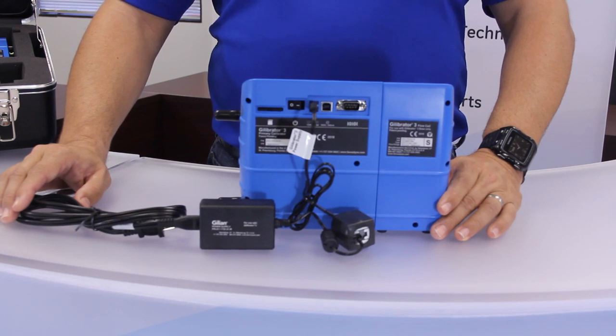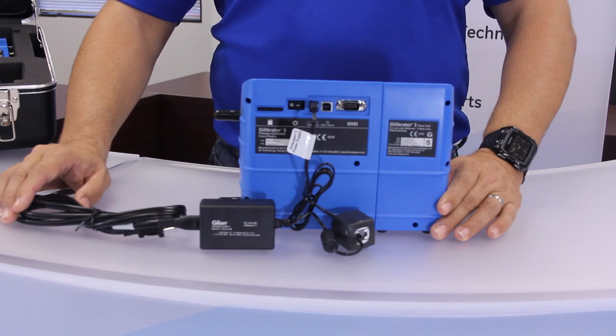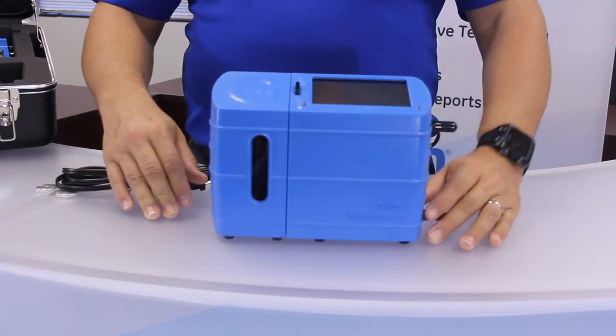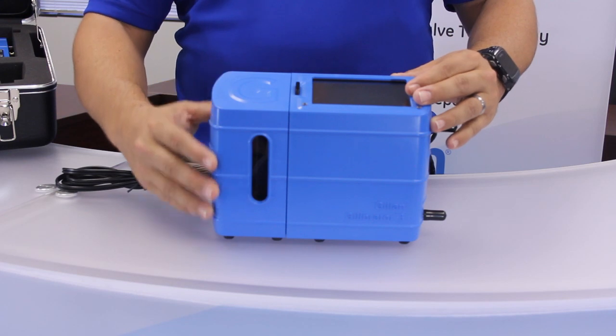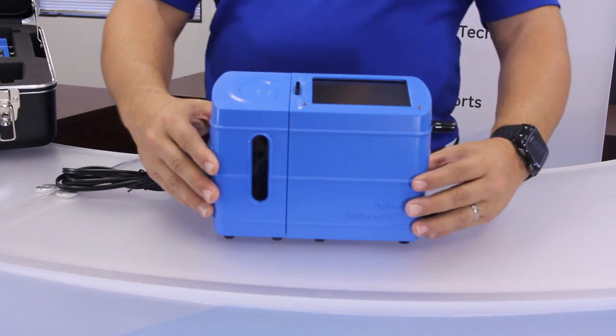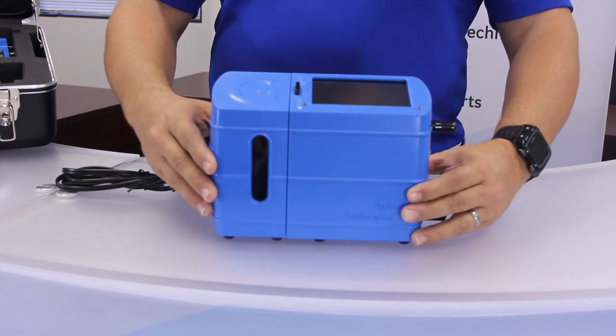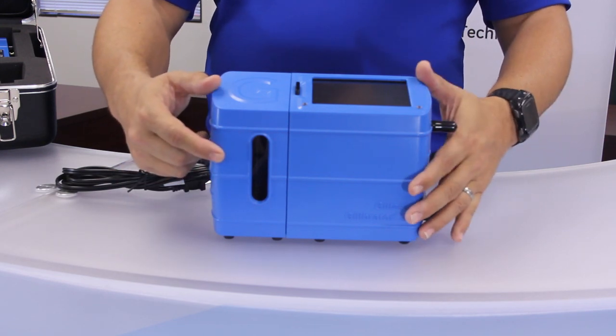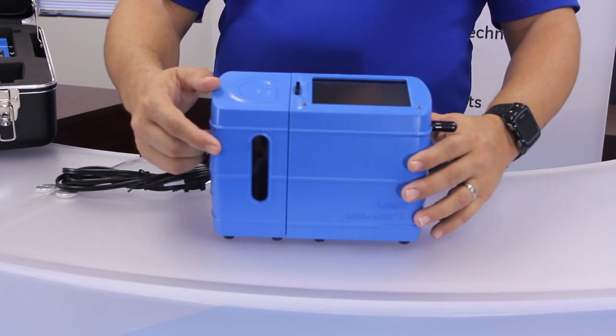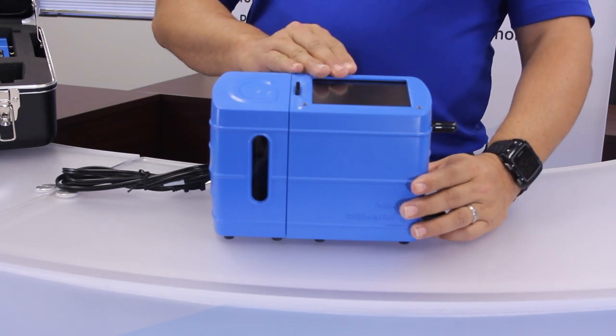If the unit was fully charged and unplugged and powered up, it may not show 99%. To reset this fuel gauge, simply plug the charger back in while the unit is on and wait for it to indicate that the battery is full. The battery capacity will be reset to 100% automatically. The battery runtime is strongly affected by the flow rate, as the actuating valve in the base consumes most of the energy. The LCD backlight is another viable power consumer, so if more runtime is needed, the user should lower the backlight level.